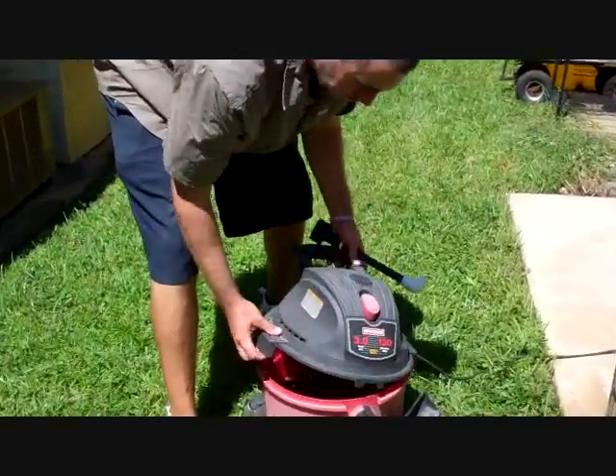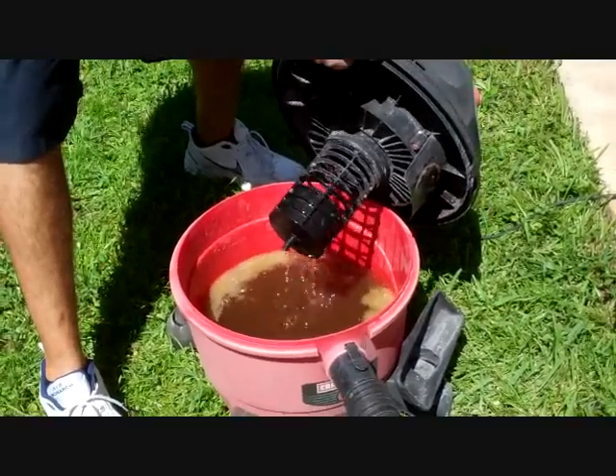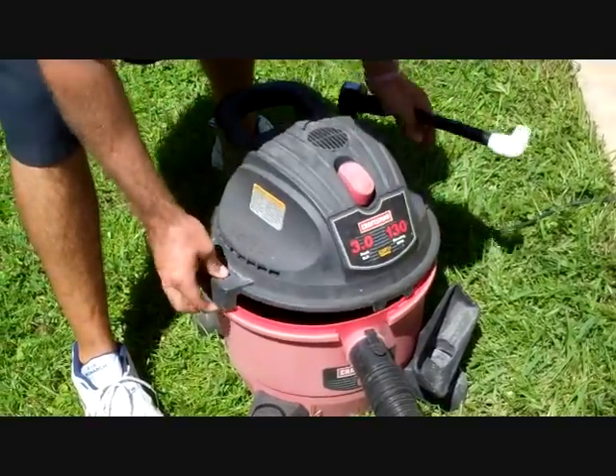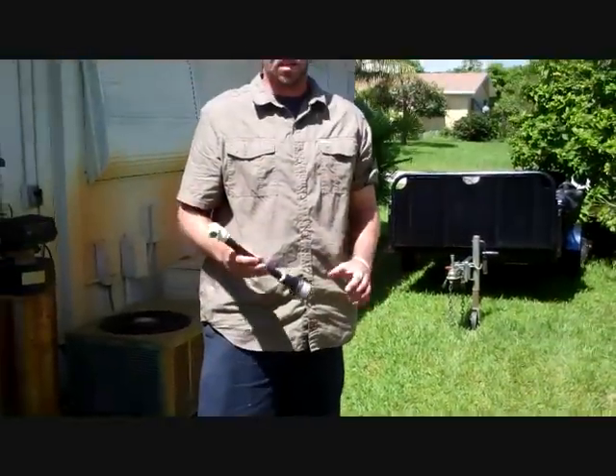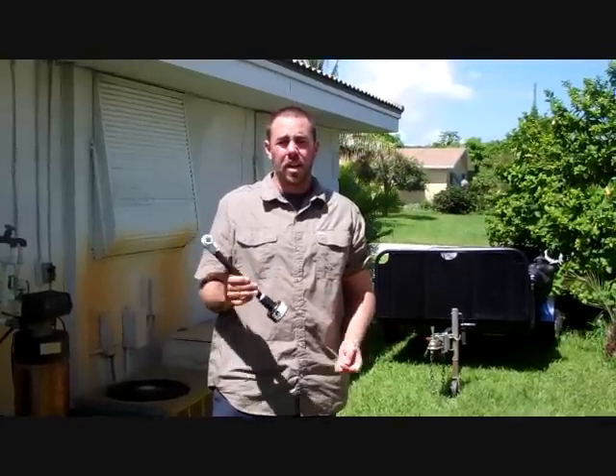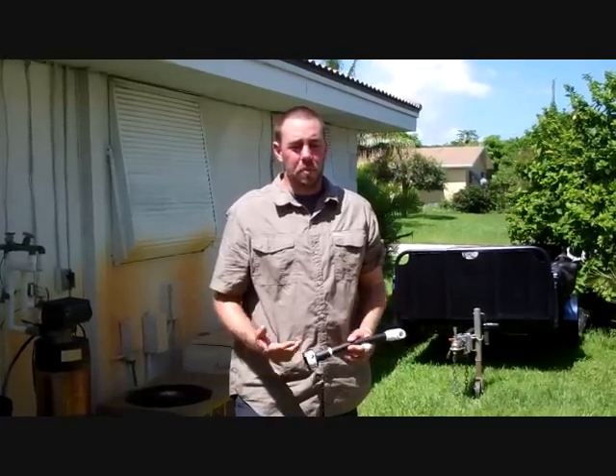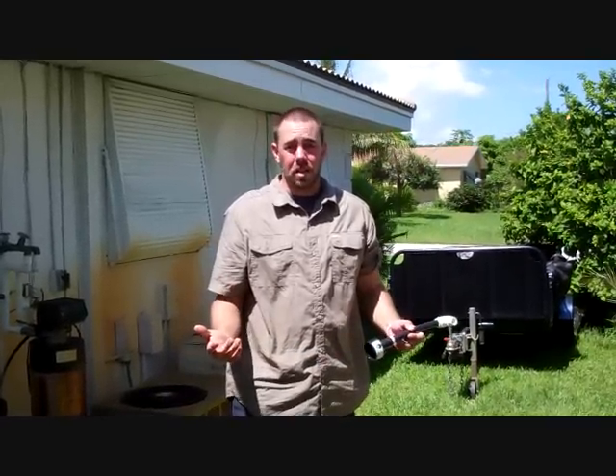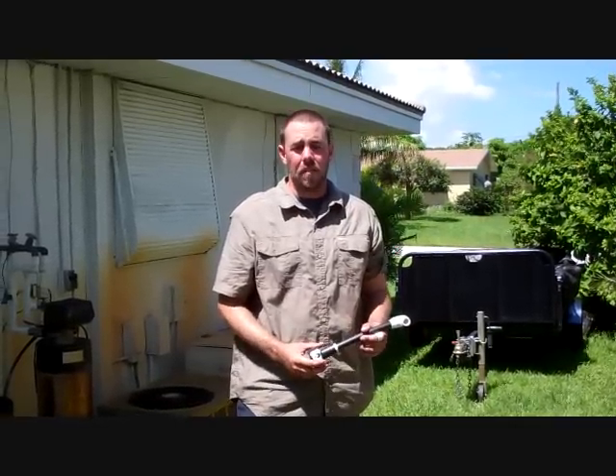Just like that — a bunch of algae water, just like I suspected. So just an overview: this took about five minutes. I got the DIY Vac on eBay for $20. The standard service call for this would be roughly about $150. I hope this helps all of you out there — have a good day.